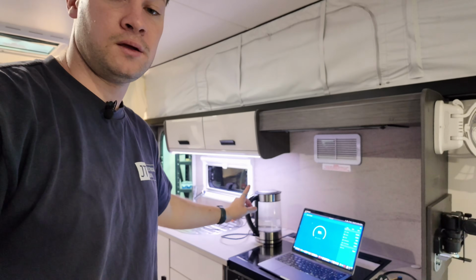As you'll see, I'm going to put a little pressure test on this system running at 4,000 watts for about 1.5 to 2 minutes, running this air heater and this kettle behind me. Things get hot at that, but these batteries are good enough to handle it, and these inverters are good enough to handle that.